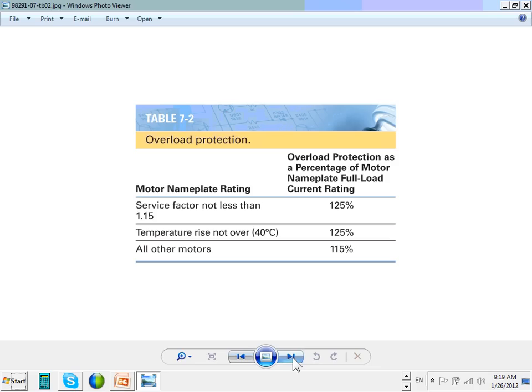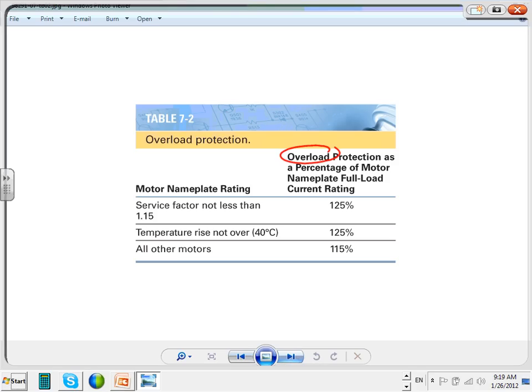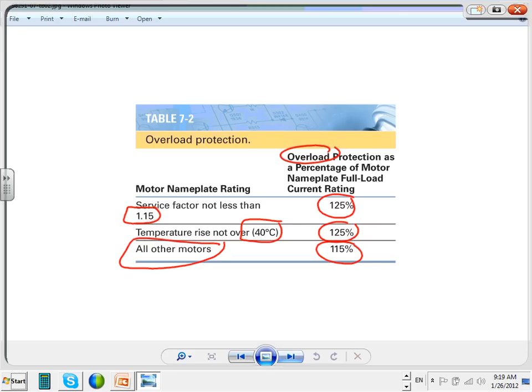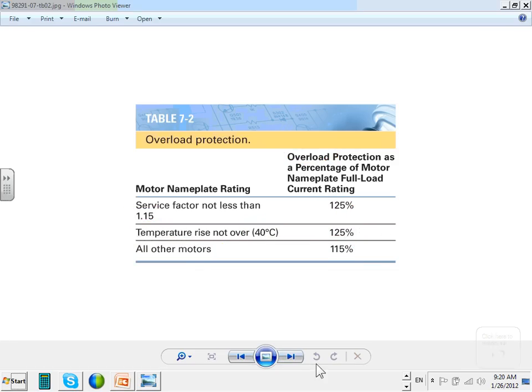Nick, my friend, remember you asked me about how do you size the overload? Here's your overload multiplier. You're going to use, for all other motors, 115%. This is from the code. And if the temperature rise is 40 or less, 125. If the service factor is not less than 1.15 or larger, 125. Almost the default is 115. The exception is 125. Any comments, guys, about sizing overload? I know we did size overload last quarter, and we will continue to size next quarter. You guys will come and visit these again to size overload.